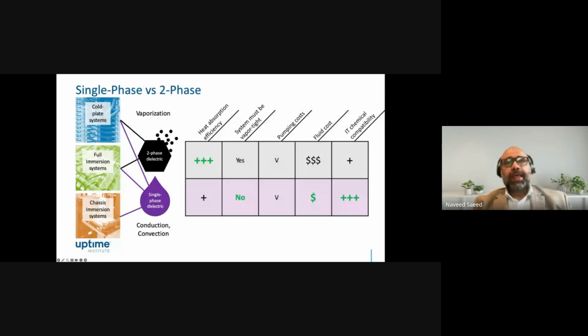In immersion cooling, two-phase dielectric fluid claims that they don't require any pumping, but there are some pumping costs associated with the single-phase dielectric fluid. If the two-phase dielectric fluid is used for a cold plate, then pumping costs are there. So it depends. It varies with what kind of infrastructure is being used for these dielectric fluids. The fluid cost is much higher for two-phase dielectric compared to single-phase dielectric fluid, and the IT compatibility of single-phase dielectric fluid is proven to be wider than two-phase dielectric fluid. So that's a bit of comparison of the benefits of each type of dielectric fluid.